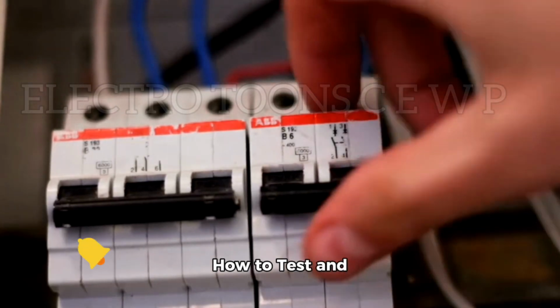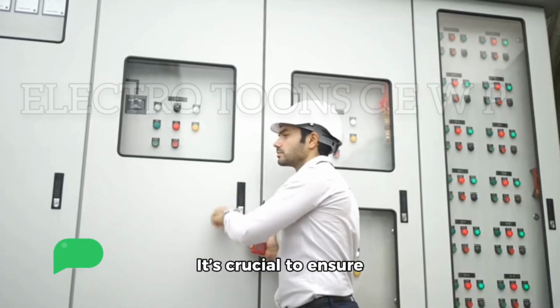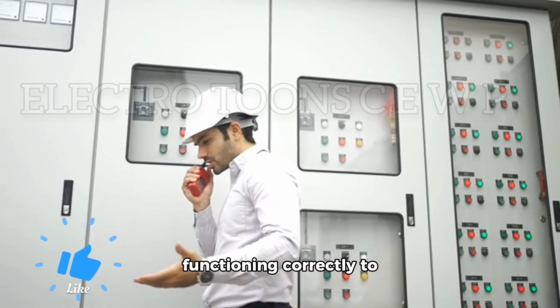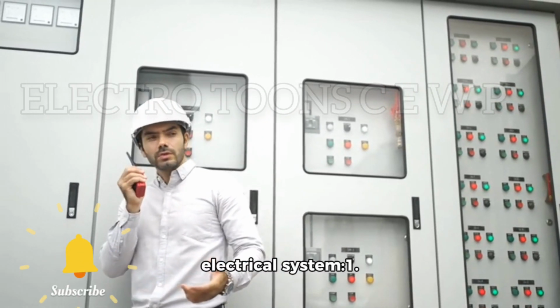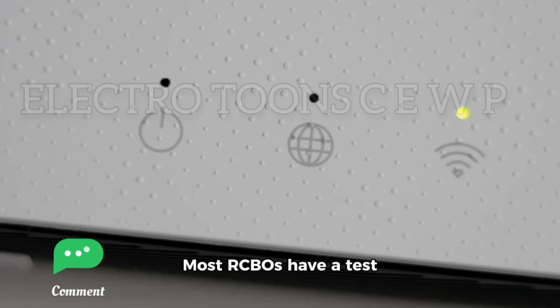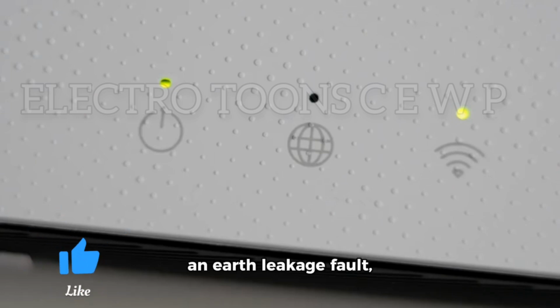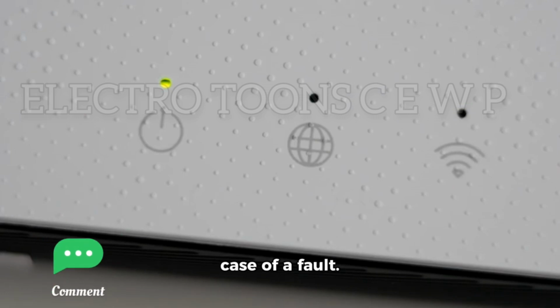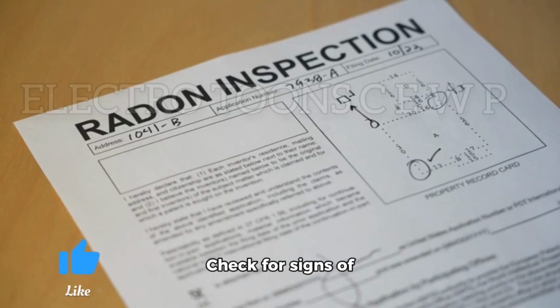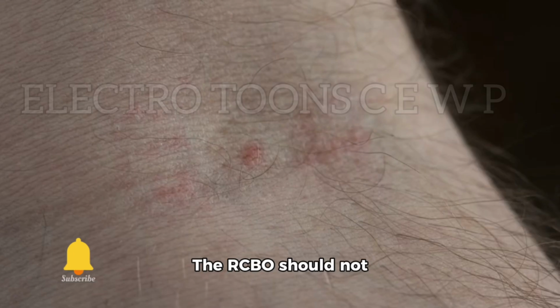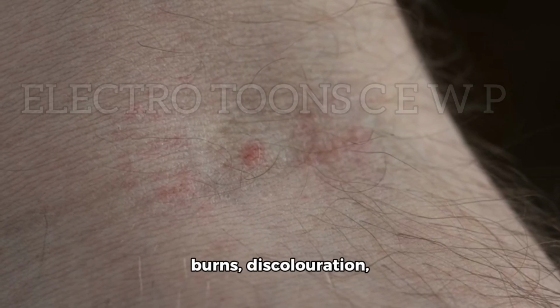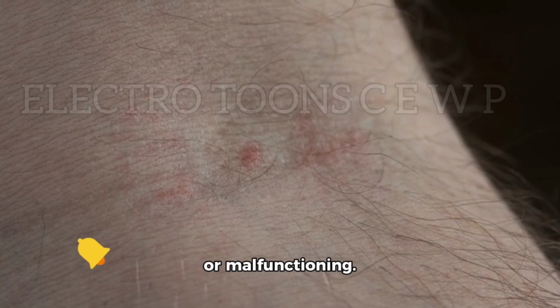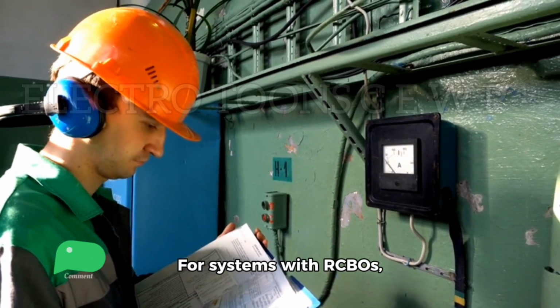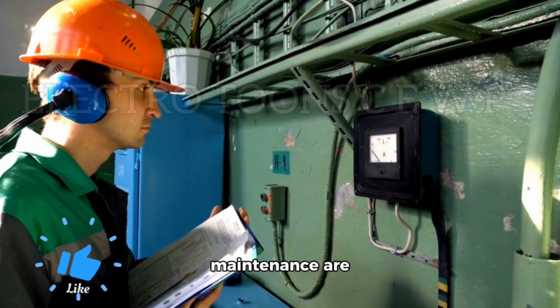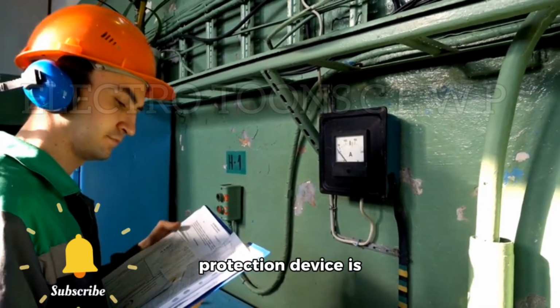How to test and maintain an RCBO. It's crucial to ensure that an RCBO is functioning correctly to maintain safety in the electrical system. 1. Testing: most RCBOs have a test button that simulates an earth leakage fault, allowing users to verify whether the device will trip in case of a fault. 2. Visual inspections: check for signs of physical damage or wear. The RCBO should not show any signs of burns, discoloration, or malfunctioning. 3. Regular maintenance: for systems with RCBOs, regular testing and maintenance are important to ensure the protection device is working as intended.